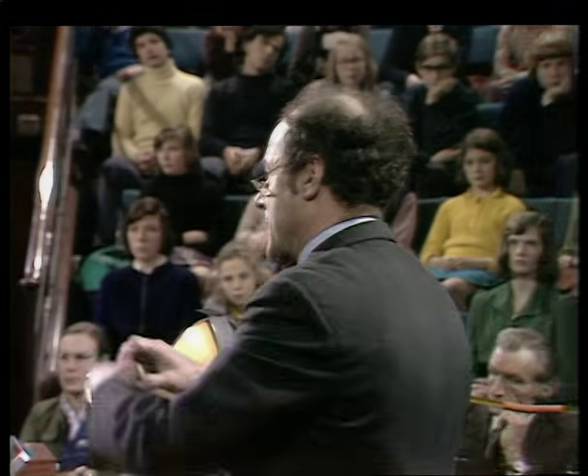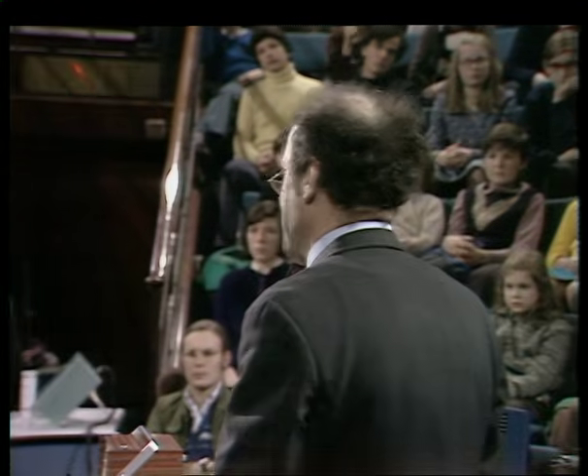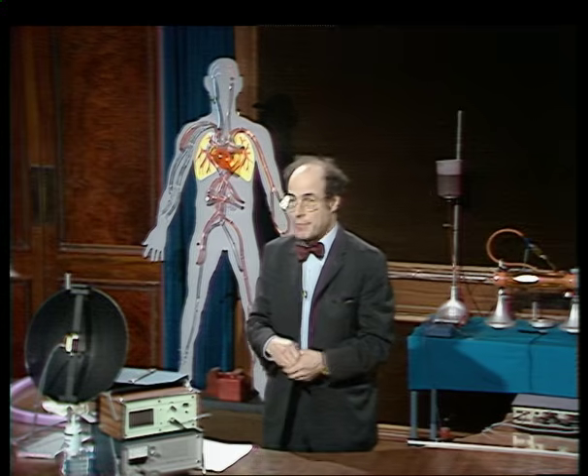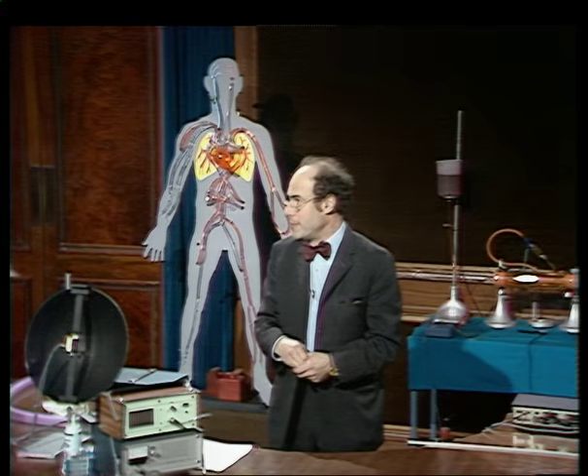If I were a central heating engineer wanting to measure the pressure of my pump, all I'd have to do is take a spanner, undo one of the union nuts, and put a pressure gauge in the way—and there's my measurement.